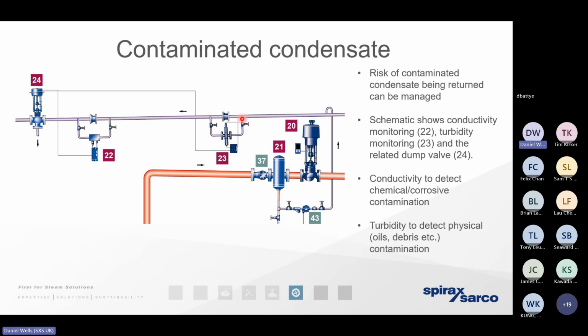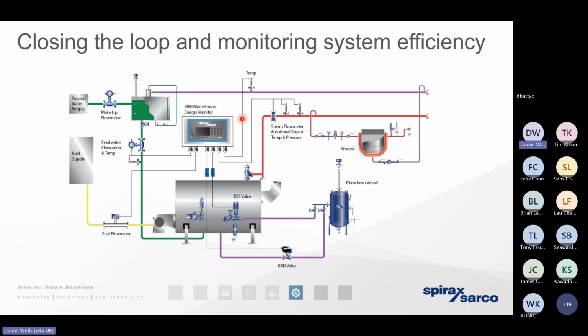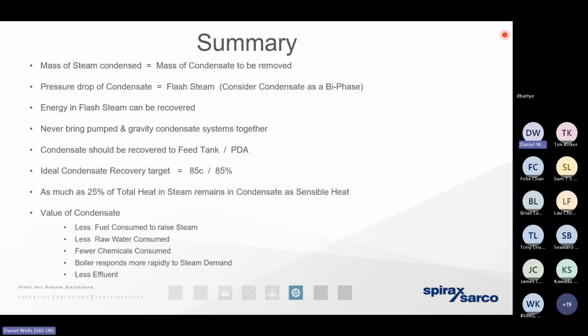And of course, if we've got steam condensate that is being dumped to waste through a fear of contamination, we can use a series of turbidity or conductivity probes. It really depends upon the nature of the contaminant, in order to ensure that whilst that hot water is in a good condition to be used, we can do so. So it really comes down to closing that loop. One of the most important things we can do to ensure the steam system is working as efficiently as we can is by ensuring that we get as much of that vitally important hot water back to the boiler house for reuse. So takeaways really from today's presentation, please remember that rule of thumb. In a traditional steam system, we should be aiming to recover about 85% of the condensate so we can keep the temperature of the hot well at about 85 degrees.